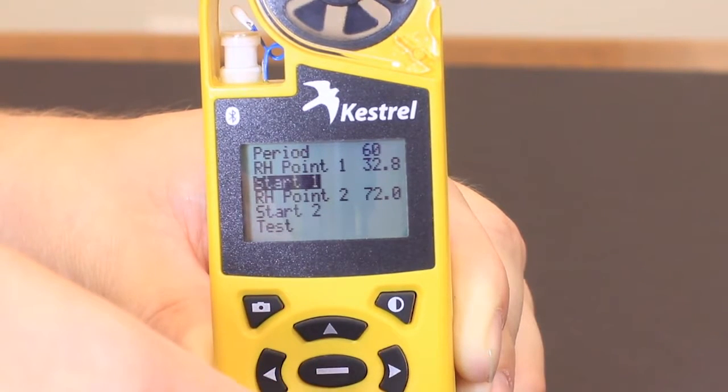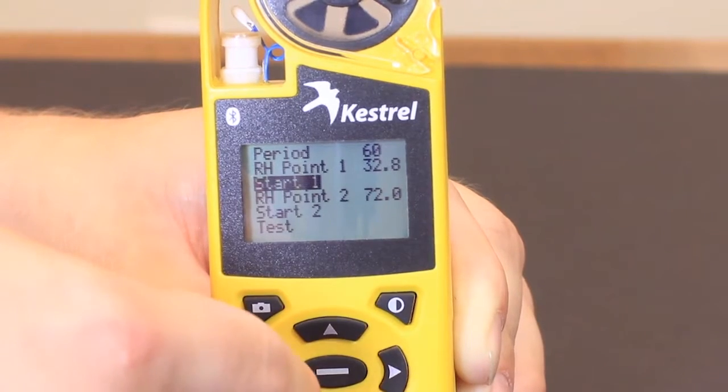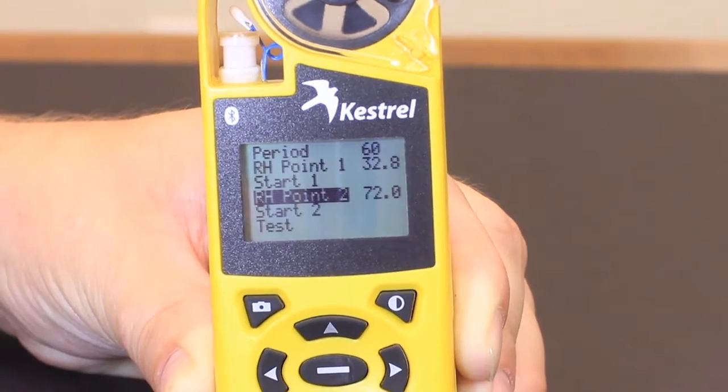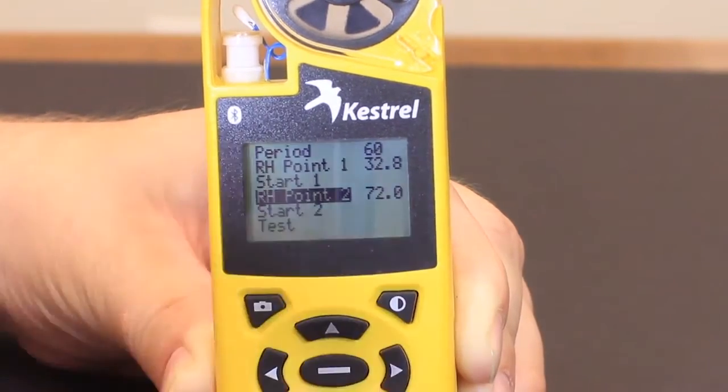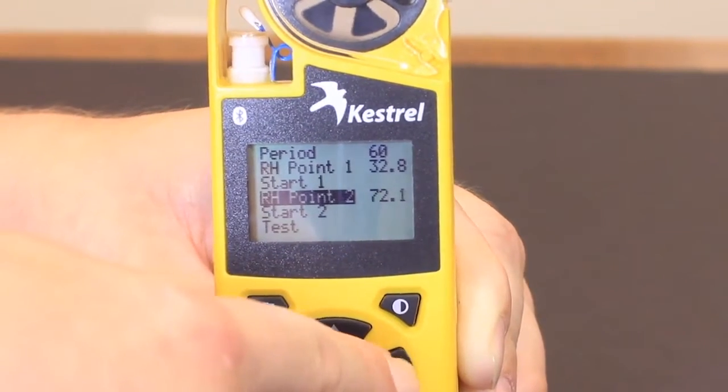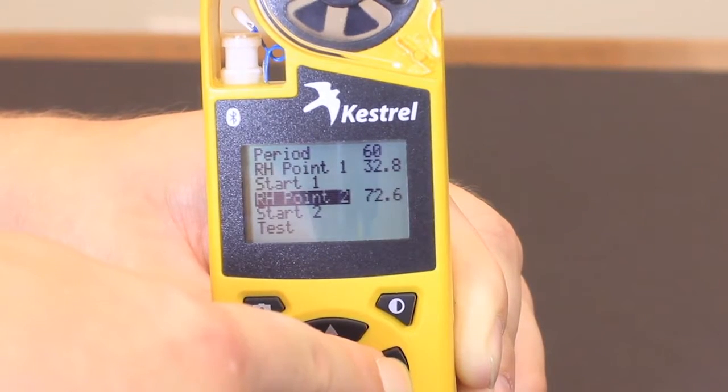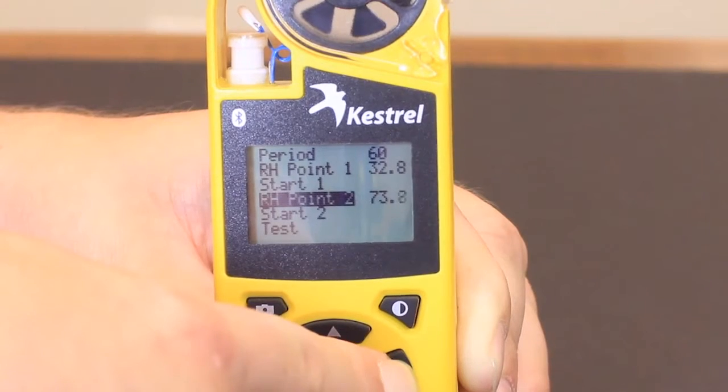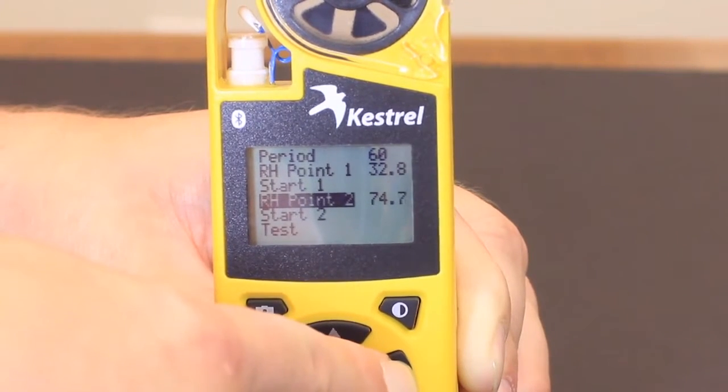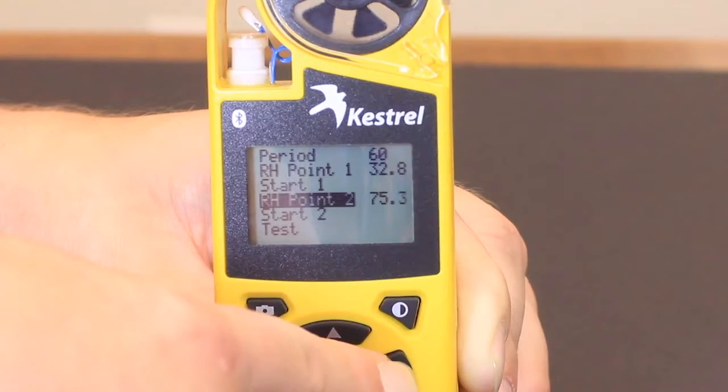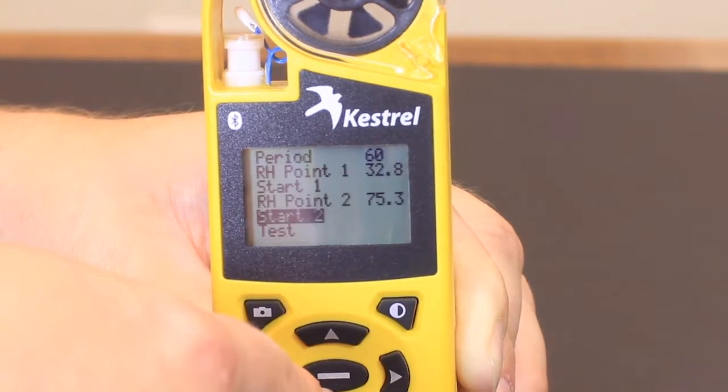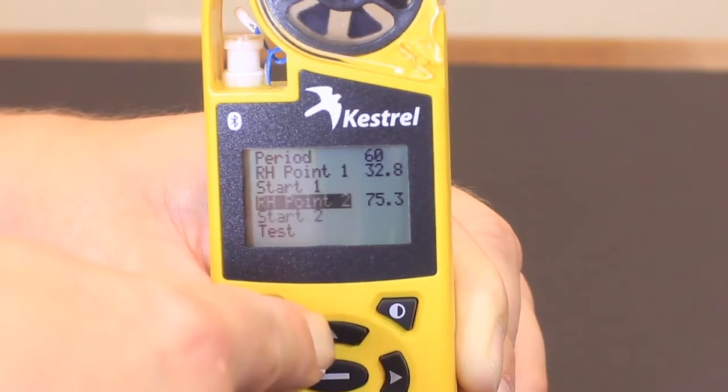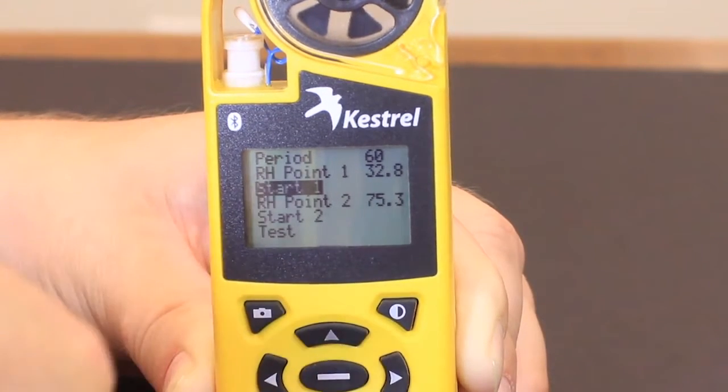Start 1 is when we're ready to do the first tank, but first we want to look at our second RH point and make sure that says 75.3. It says 72, so we're going to up it until we get the 75.3 to match what's found in the sodium chloride chamber.